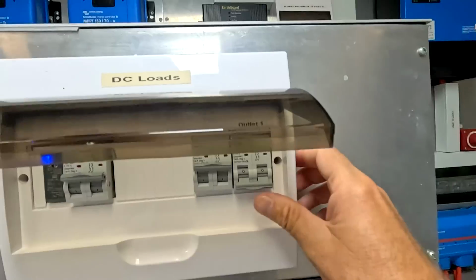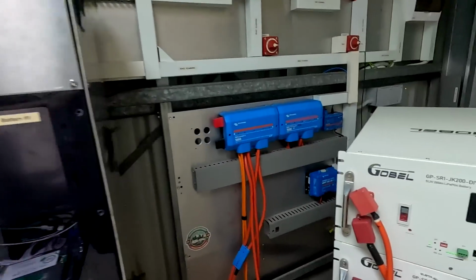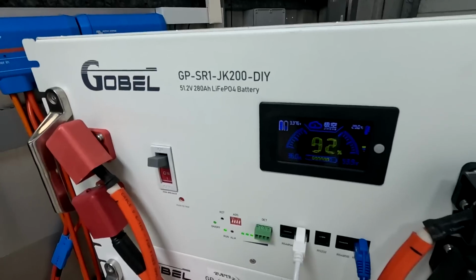Even though the Gobel tower has a far less optimal connection to the whole system. And if you're ever wondering how long such a 63 amp circuit breaker lasts with 80 amps of load on it, well, about an hour, and now it has just tripped. So I'm turning this one back on. It is probably heated up now and will trip again. So I have to limit the charge current into the Gobel tower again a little bit so the circuit breaker actually lasts. We are very close to 55.2 volts anyway, but it is just a bit too much for this circuit breaker.